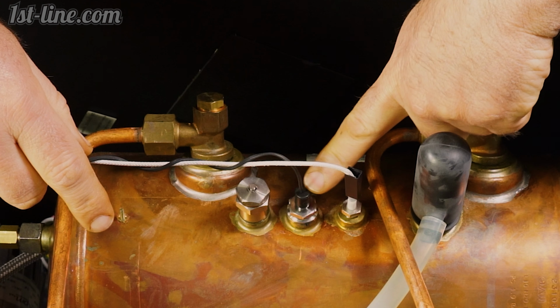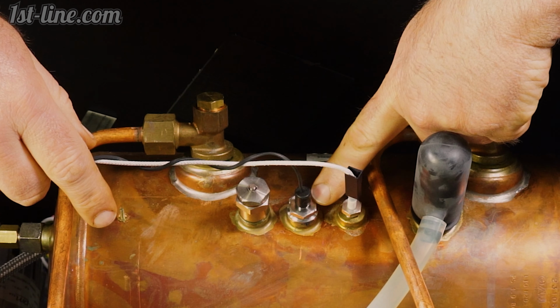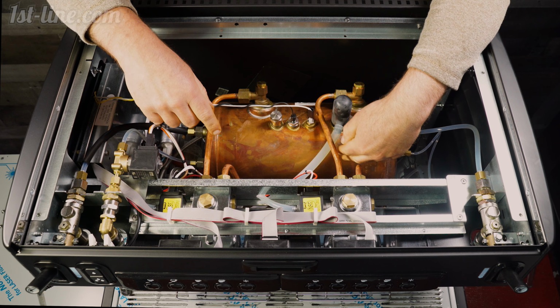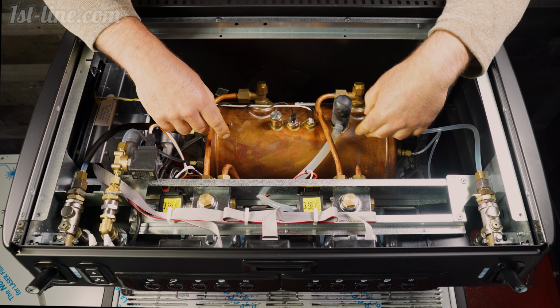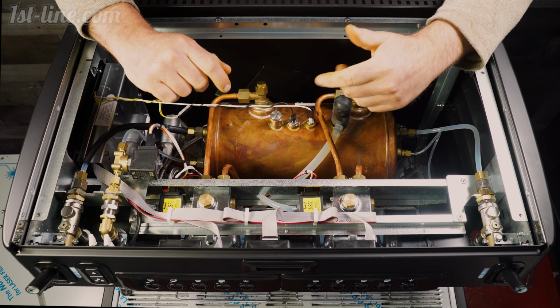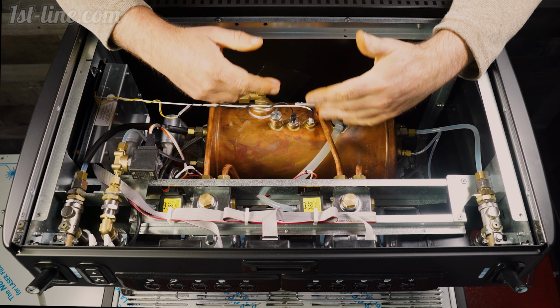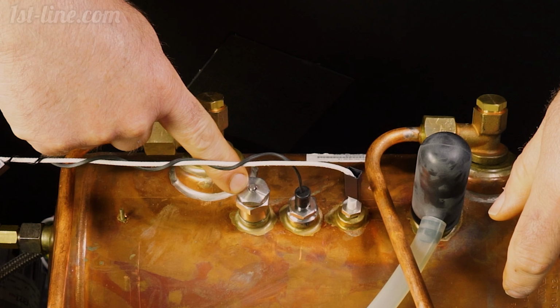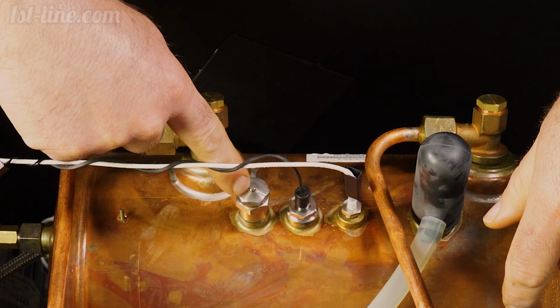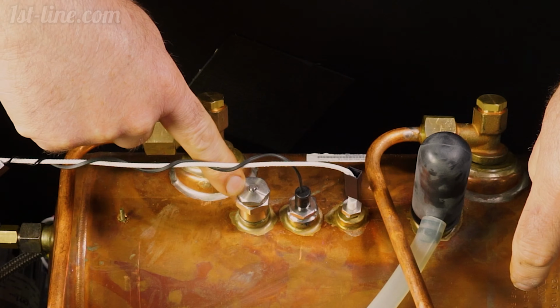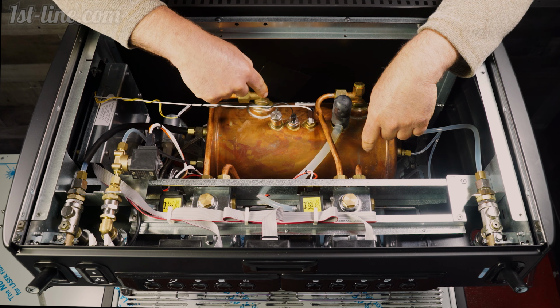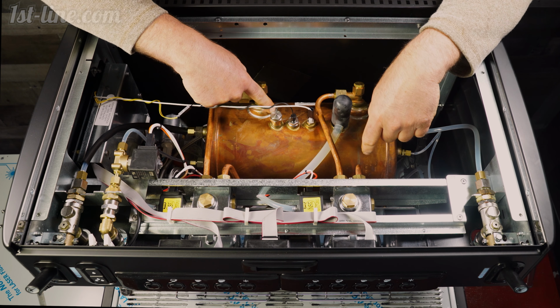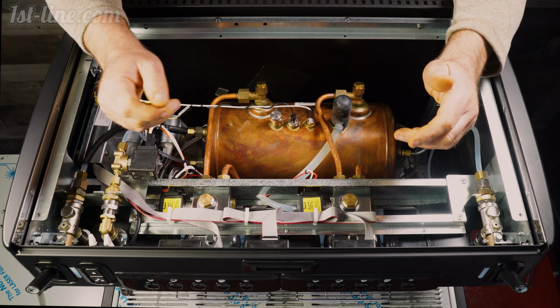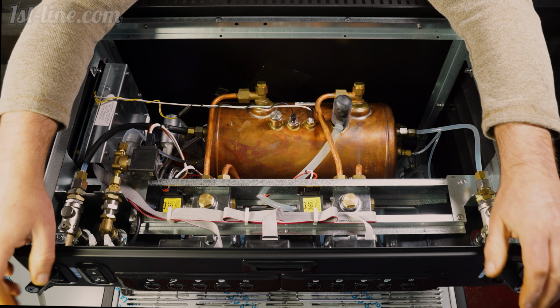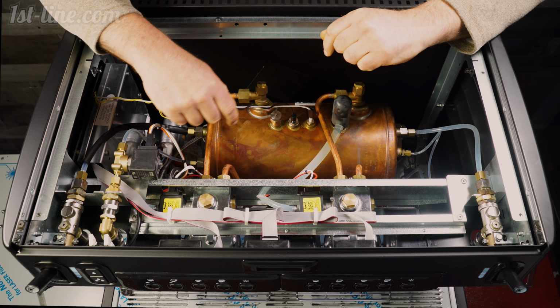Here's your PID sensor for the boiler. This is at the steam temperature. And typically the boiler will be filled half with steam and half, the bottom half, of course, with water. As the machine is warming up, some water will sprinkle out of this bleeder valve. This is the vacuum breaker valve. If you don't have this part on a boiler, then what ends up happening is that you have a vacuum inside and you have to open up the steam valves to release that vacuum.